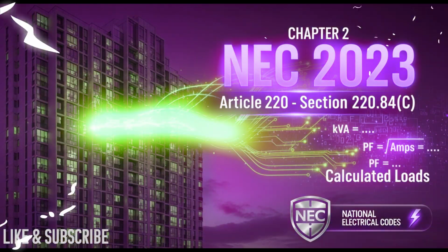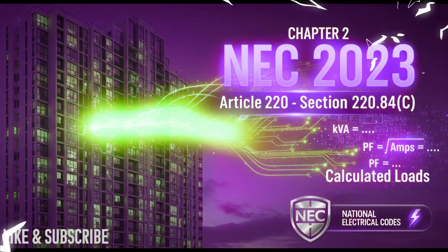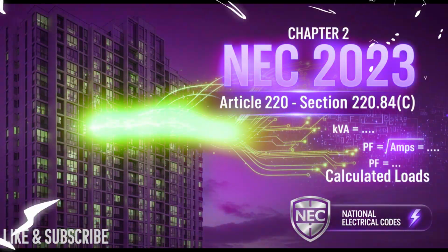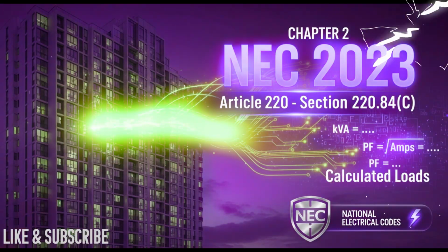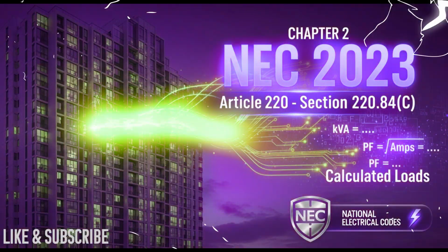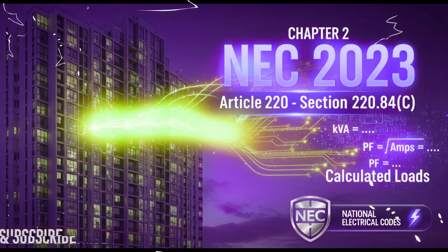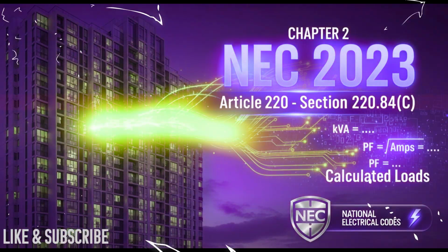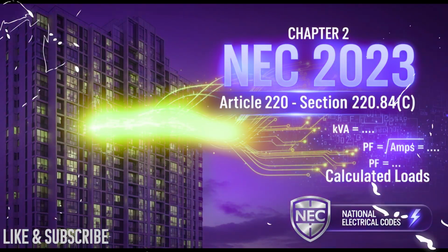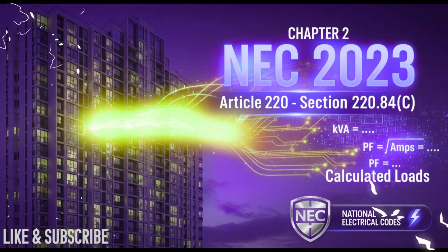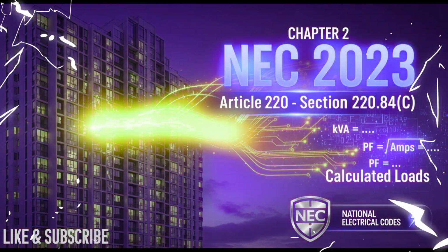They might not seem like much individually, but they add up and they run often. Absolutely. They contribute a steady or frequent demand to the building's main electrical service, so they definitely can't be ignored in this initial load calculation. Okay, makes sense. So that brings us to the last one, input 5. And this one deals with the really big energy hogs, right? Heating and cooling. The biggest variable loads in almost any building, yeah.